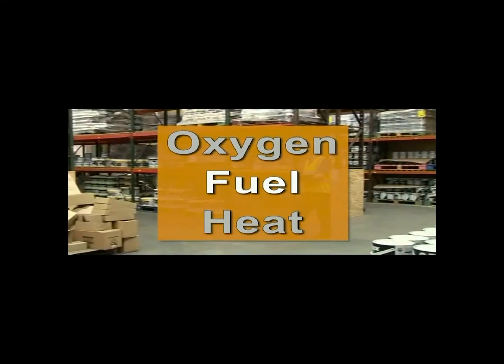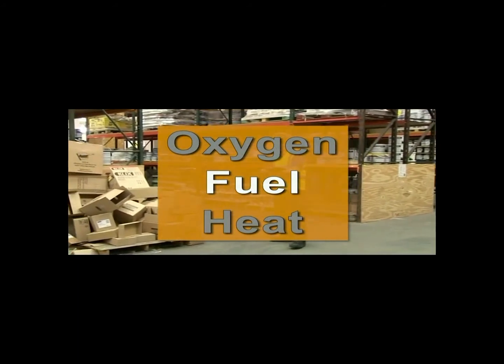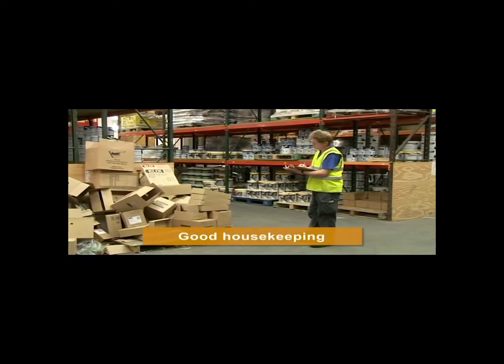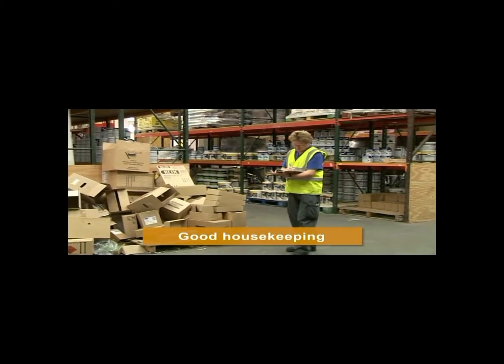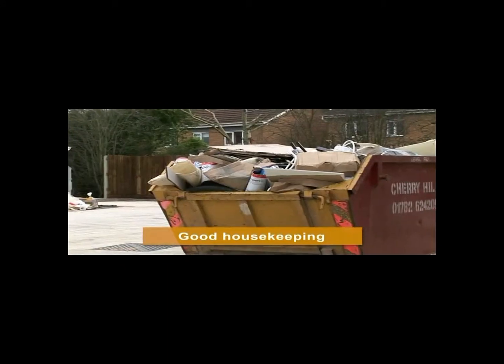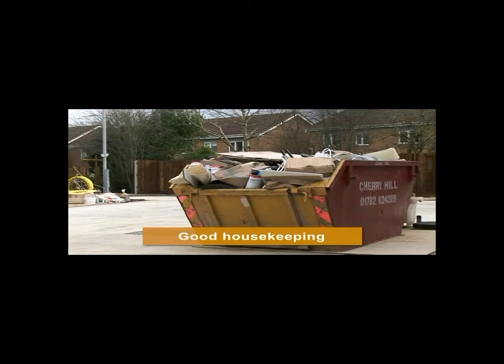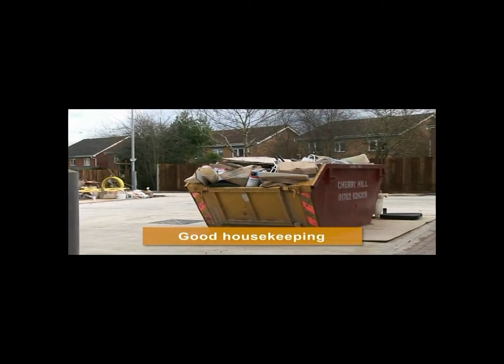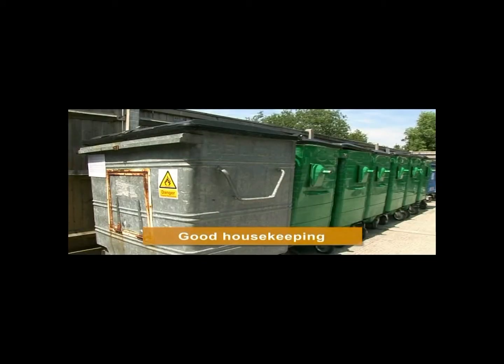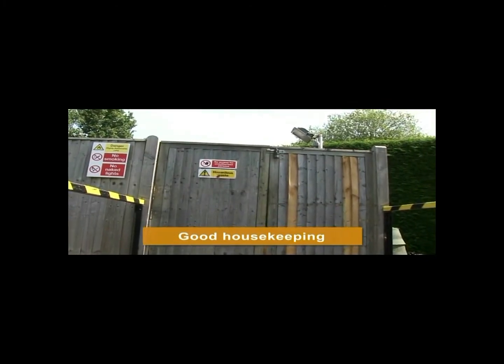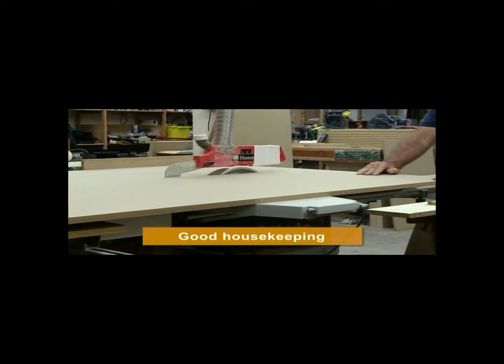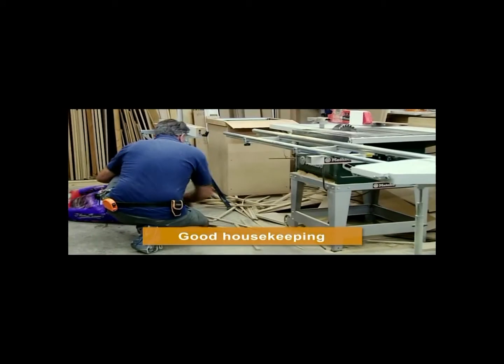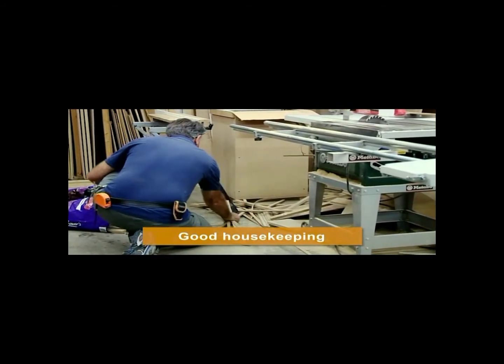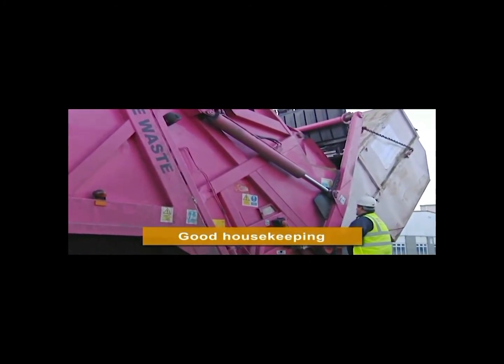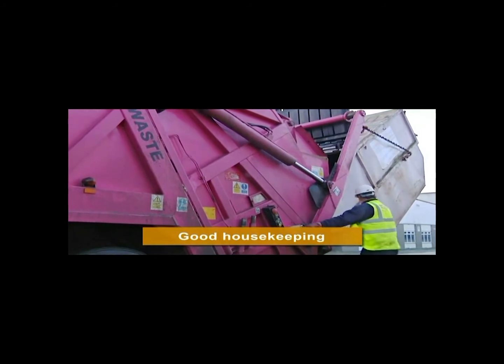When looking at eliminating or reducing sources of fuel, good housekeeping plays a vital role. Ensure combustible waste materials are not allowed to build up and that they are kept well away from buildings and boundaries. Bins should be chained or kept in secure compounds. Combustible waste from machines should be removed from the building as often as possible to minimize the risk of it being ignited. Arranging for regular collections of all waste and other combustibles will help reduce the risk of deliberate fire setting.